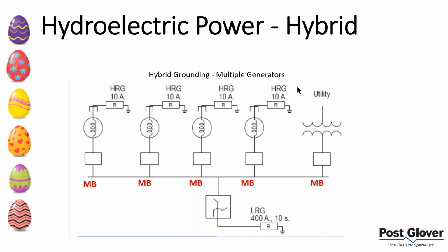But that's big, so I guess I didn't really give you an idea. Hydroelectric power is, once again, just like a generator, so I would treat it that way. The reason I bring this up is that for medium voltage generators, we almost always use resistance grounding. If you can calculate that your bracing is sufficient for your generator, then the recommendation no longer applies. That's the reason the recommendation is there. But most of the time, in my experience at least, you're going to go with the recommendation for a resistance ground. And since a hydro is in that category, I would do that as well.